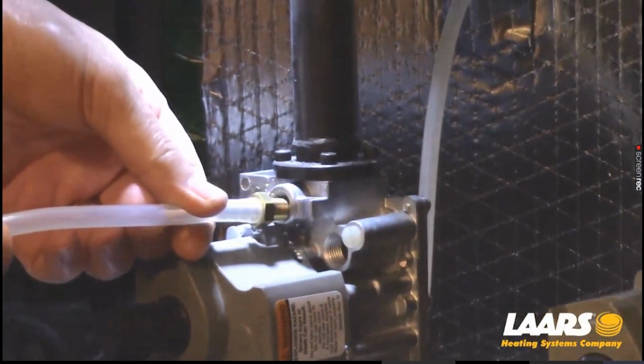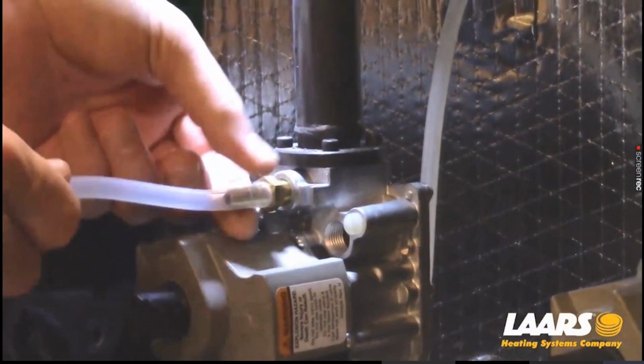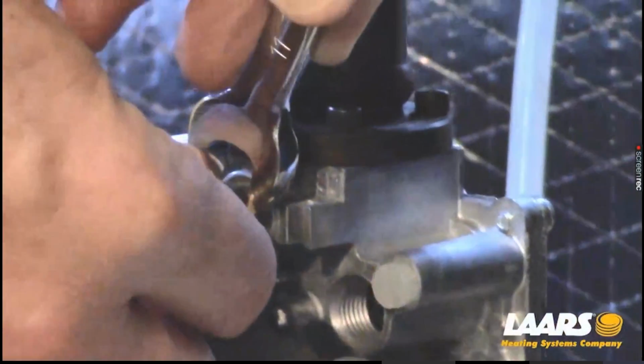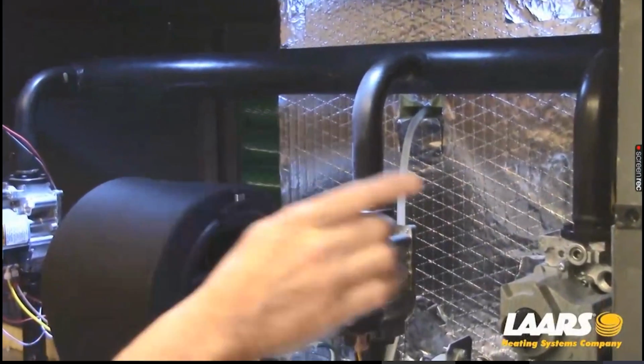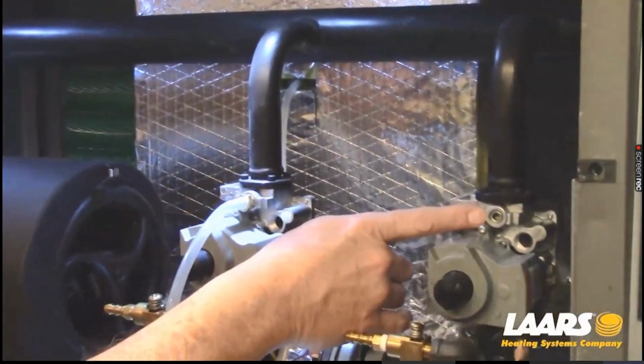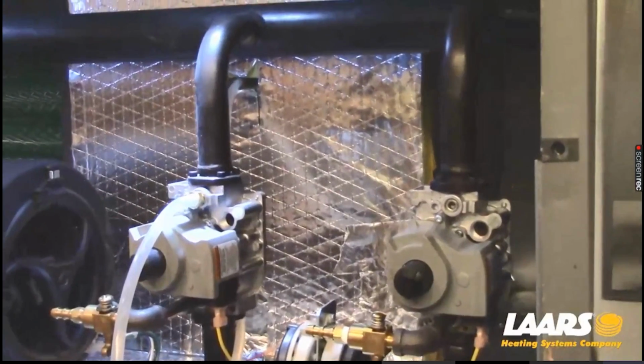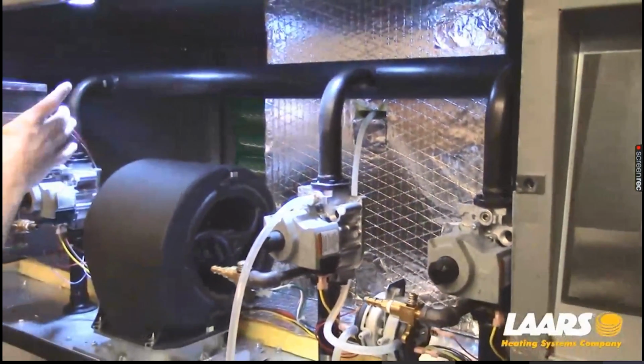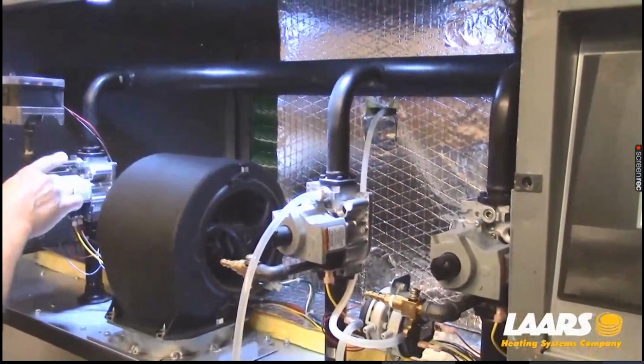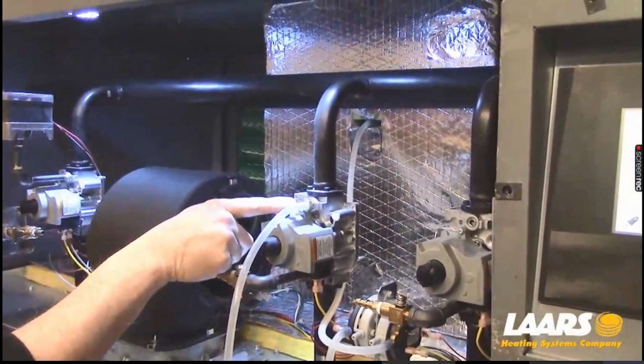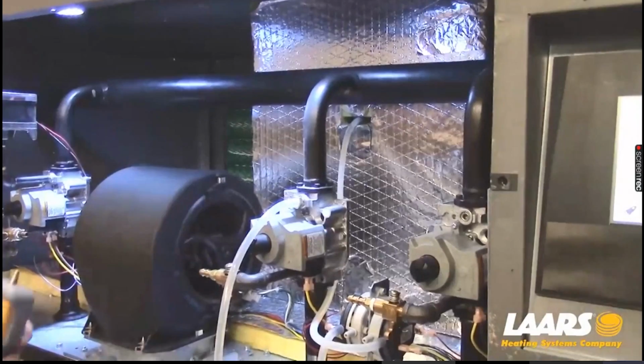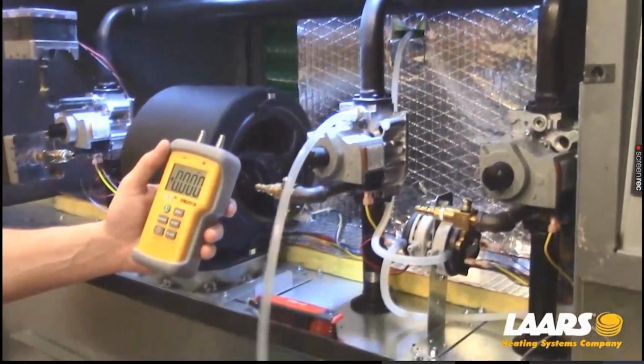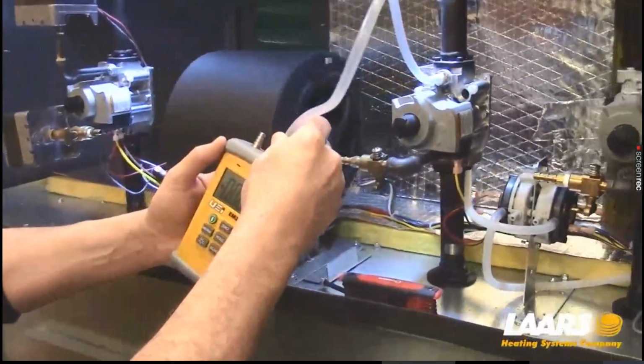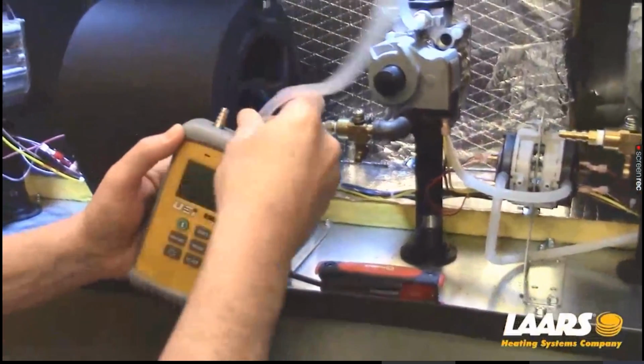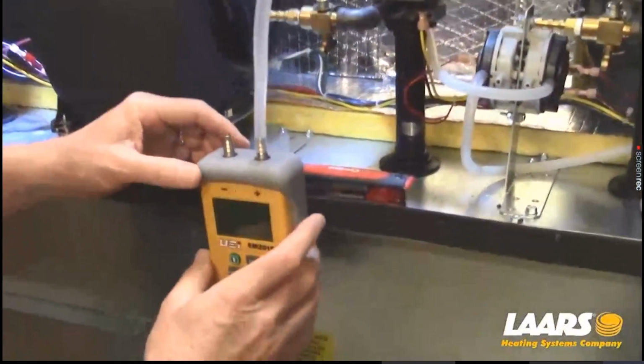Now I'll install my barb to measure my incoming gas pressure. This is a common gas train to each gas valve. And again, we have a test plug on the top of each gas valve. The boiler we're showing here is a 1 million, and it has CSD1 high-low gas pressure switches off that tap. That's why I chose the middle tap. Next, with my manometer zeroed out, I'll hook up my manometer and turn on my gas. This will show us the incoming gas pressure.